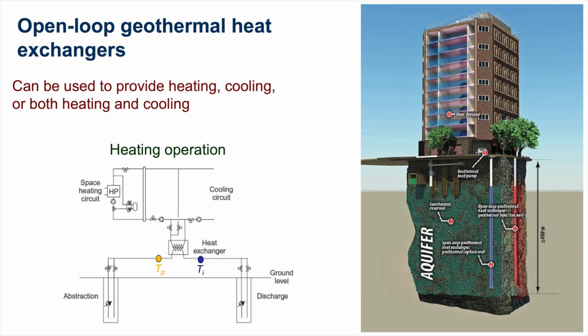We can use this to provide heating or cooling or both. For heating, we produce water at the ambient aquifer temperature and pass it through a heat exchanger—we don't pass the groundwater itself through the heat pump. We take the heat out of it, then re-inject the cold wastewater back into the aquifer.